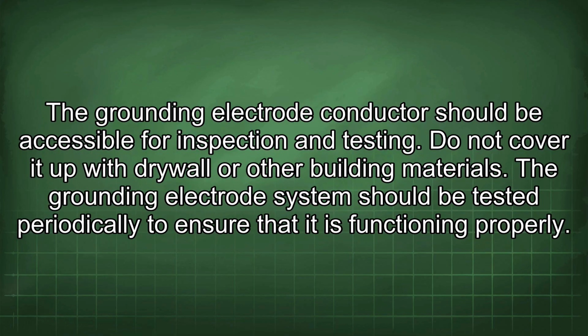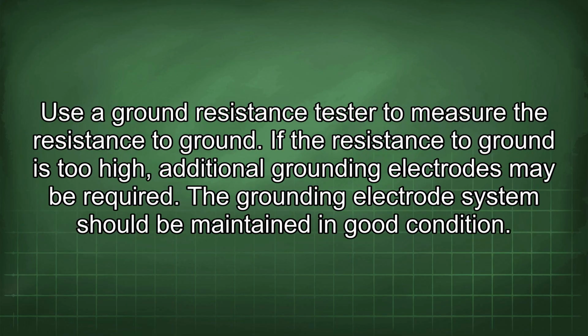The grounding electrode conductor should be accessible for inspection and testing. Do not cover it up with drywall or other building materials. The grounding electrode system should be tested periodically to ensure that it is functioning properly. Use a ground resistance tester to measure the resistance to ground. If the resistance to ground is too high, additional grounding electrodes may be required.